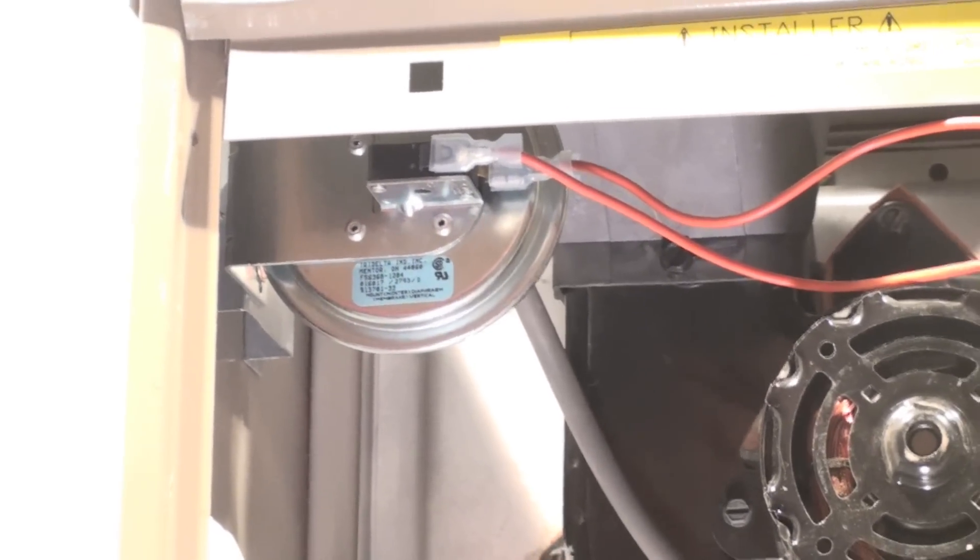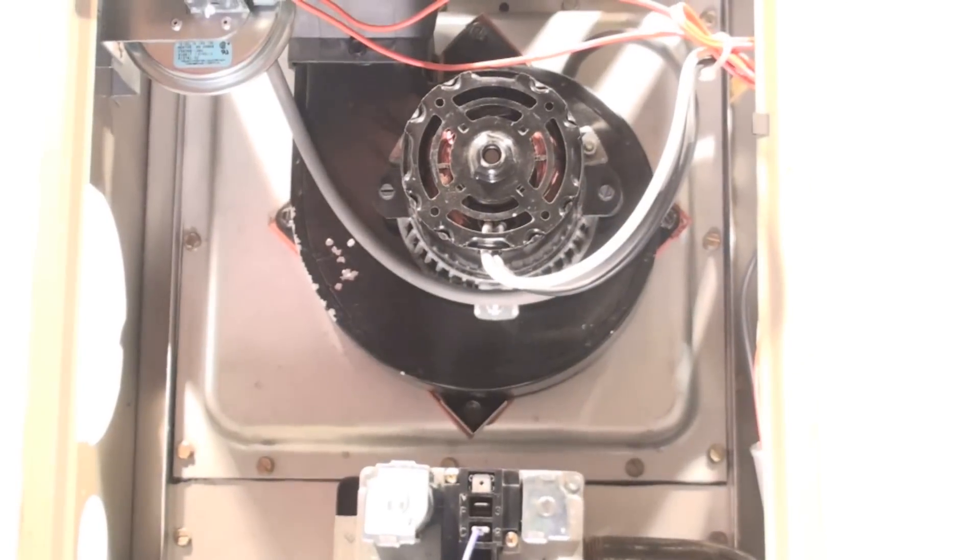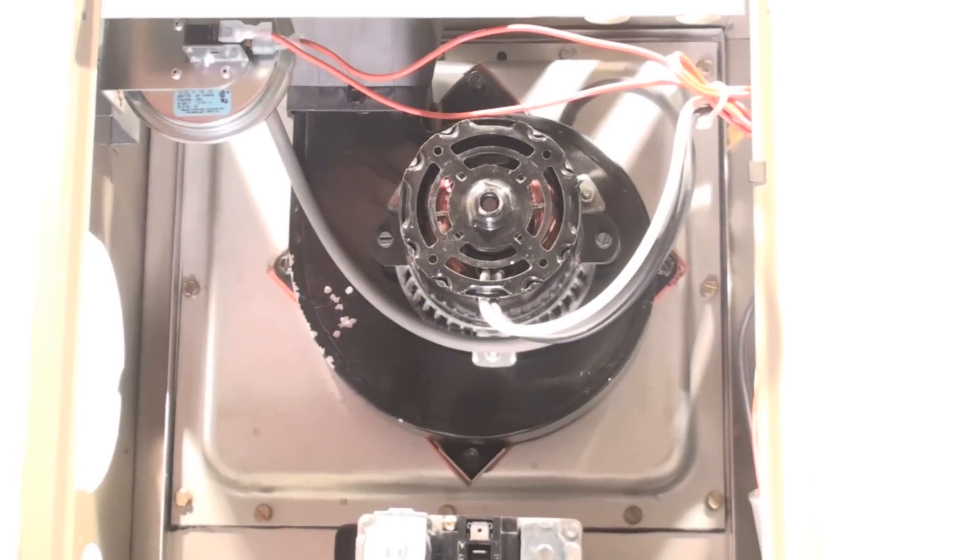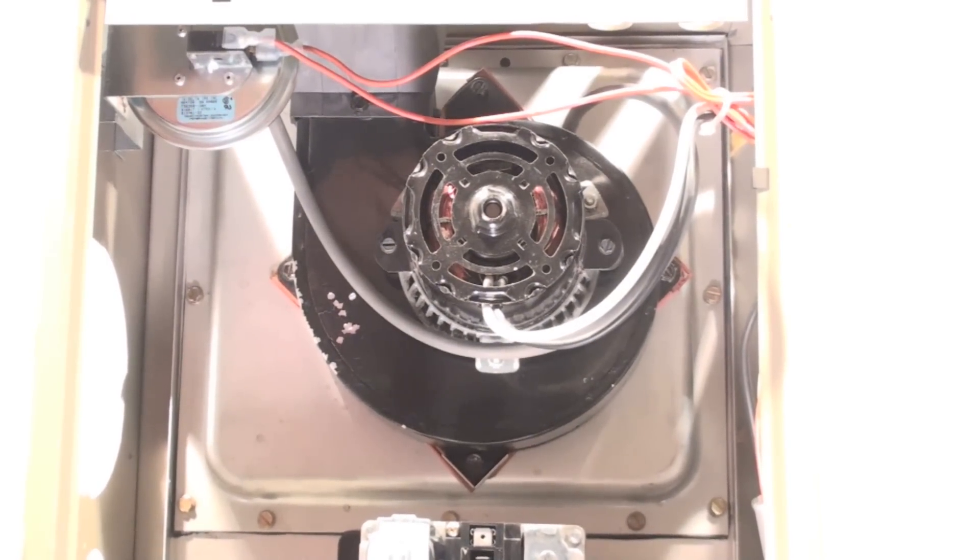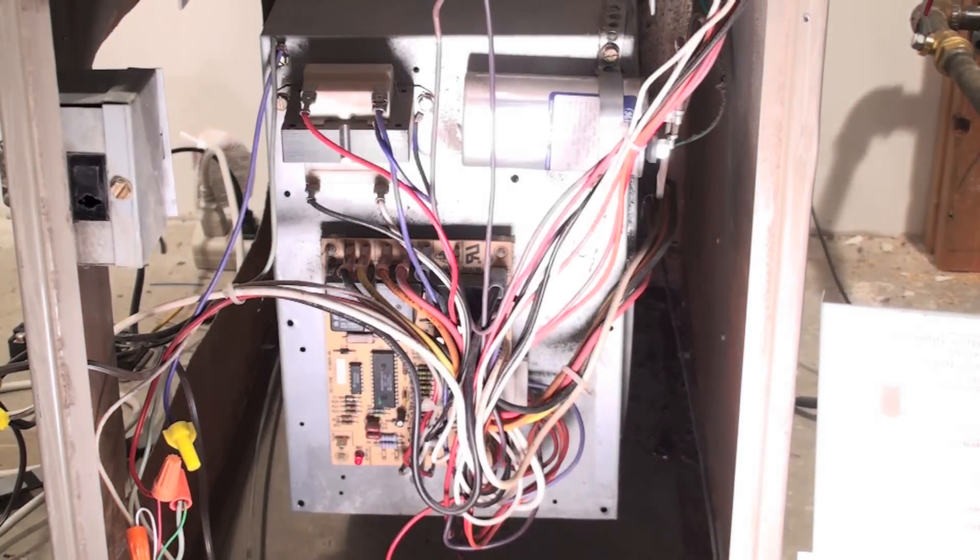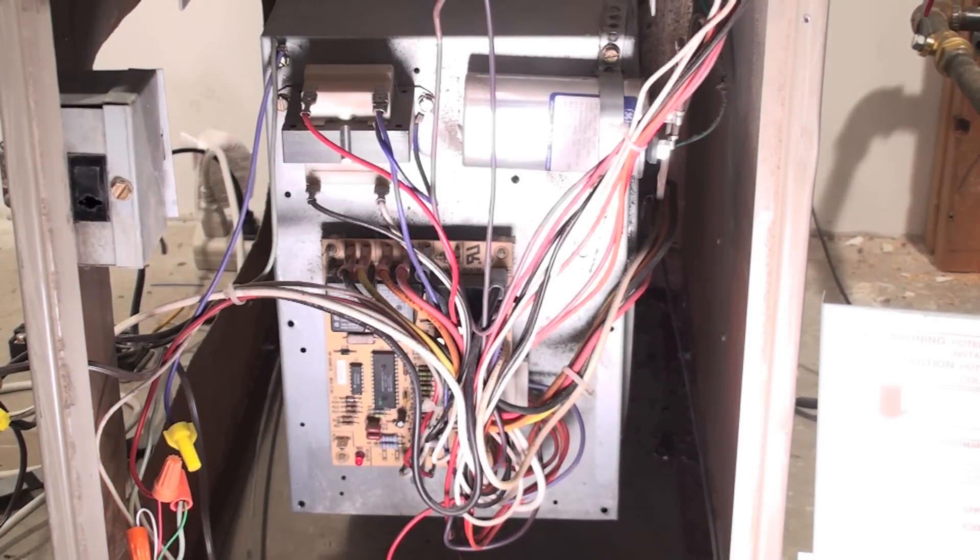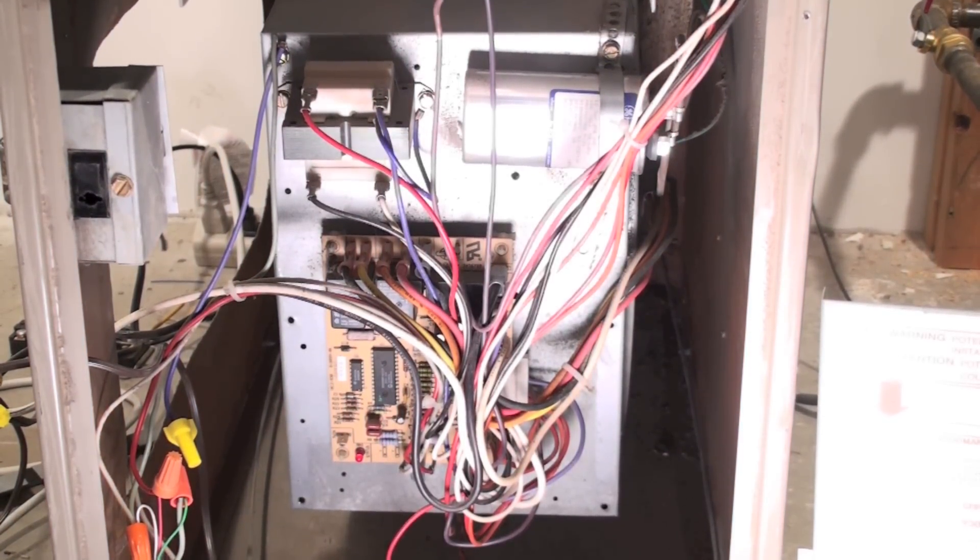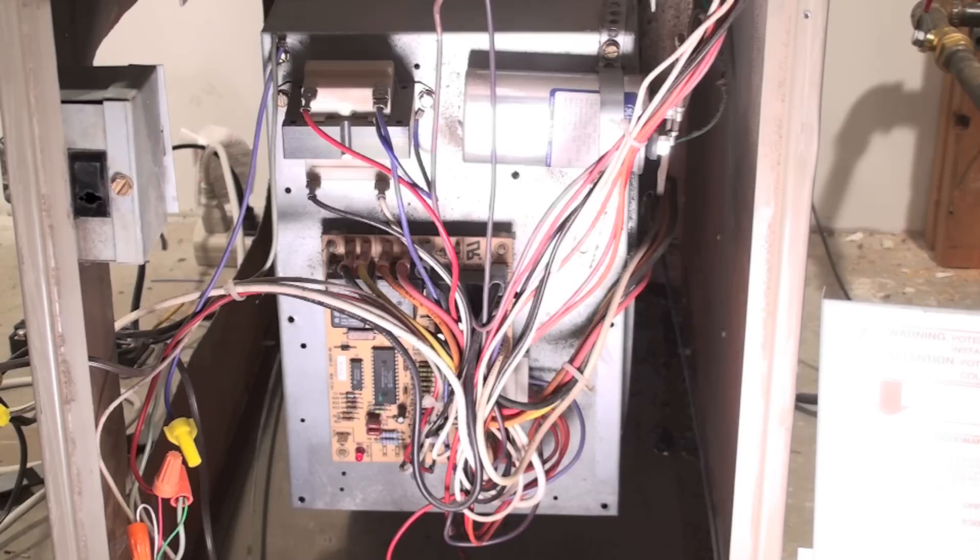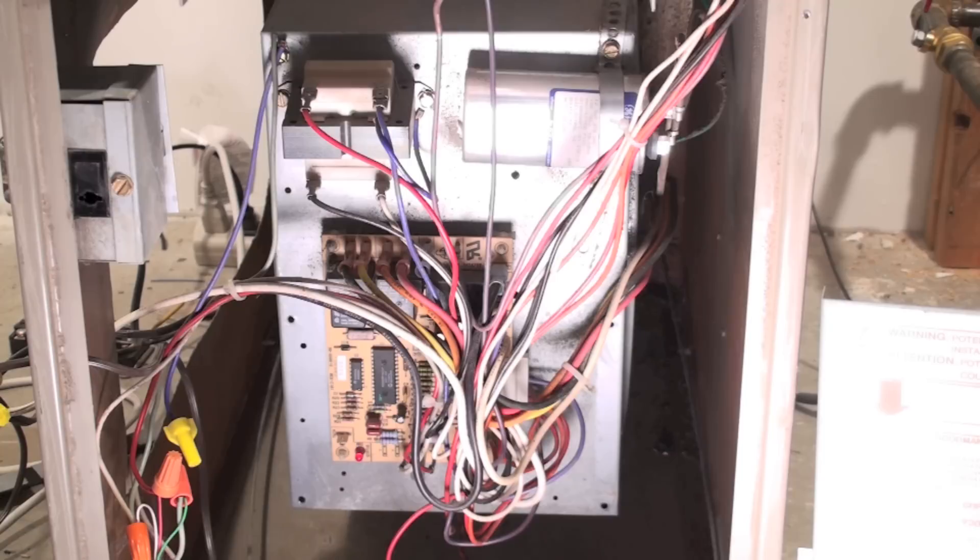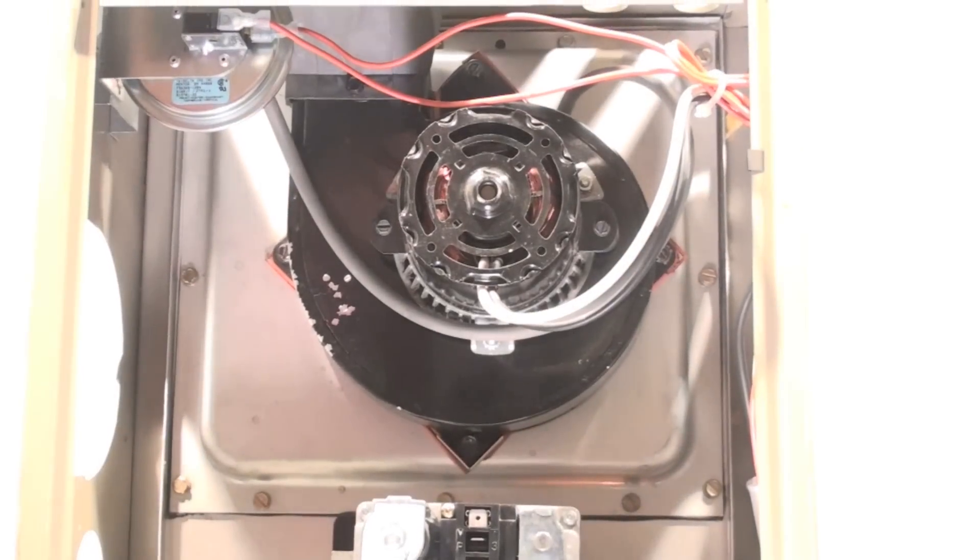On a call for heat, the inducer does not come on immediately. The board has to look at the pressure switch and see if it's open or closed. If it's closed, it goes no farther and starts blinking a code for pressure switch problem, because it shouldn't be closed before the inducer comes on.